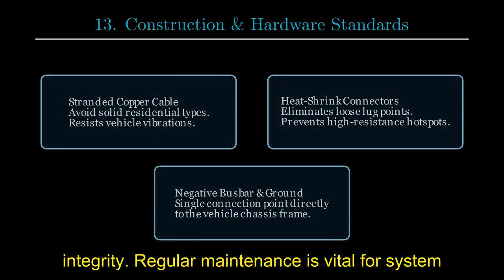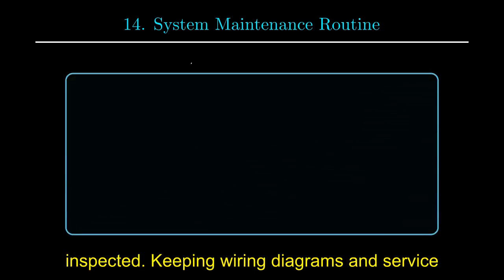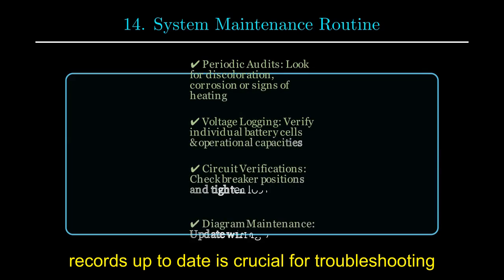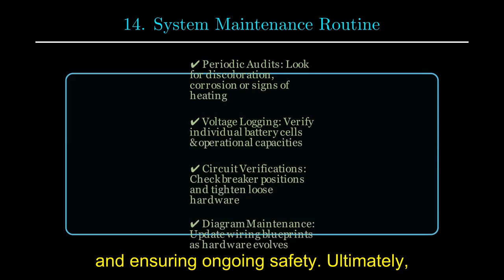Regular maintenance is vital for system longevity and performance. This includes monthly visual checks for discoloration, loose connections, or corrosion. Battery voltages and charging functions should be verified, and fuses and breakers inspected. Keeping wiring diagrams and service records up to date is crucial for troubleshooting and ensuring ongoing safety.